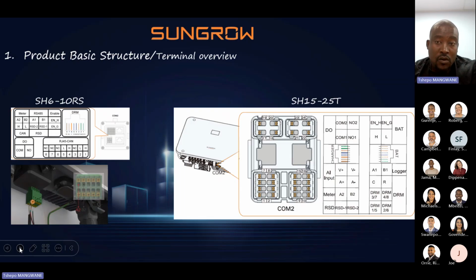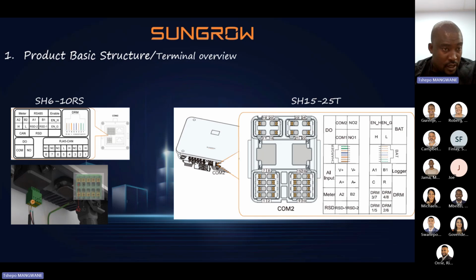Okay, now we're going to look at the terminal overview on our comms port on the single phase and the 3-phase side. On the single phase side, the 6RS is similar to the 10RS. The connections are still the same. So where do we mainly focus in terms of connections? It's our meter, CAN, RS485 as well. For the meter connection, from your meter side to the inverter, you will connect your meter on A2, B2, right? Then RS485 comes on A1, B1. And also we have CAN high and CAN low, which is our battery CAN communication. You'll see in the manual, they will say orange and white is our CAN high. Then solid orange will be our CAN low.